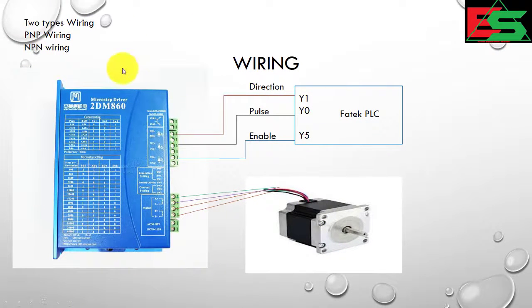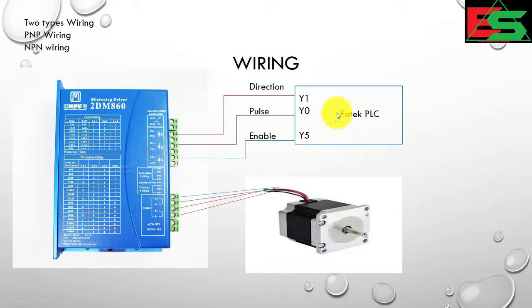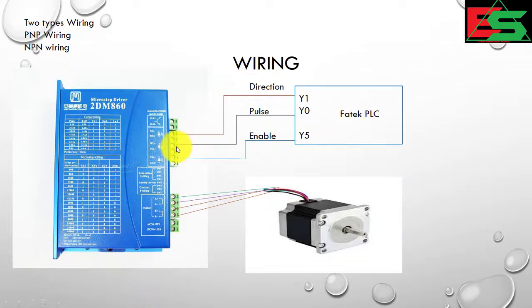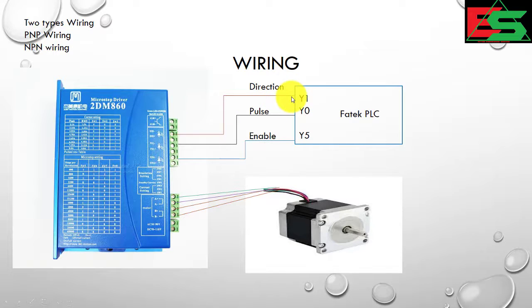Now for wiring - there are two types: PNP and NPN. In this slide I will show the basic wiring between Fatek PLC, driver, and motor. You can see here the Fatek PLC outputs Y0 and Y1. Y0 will generate pulses and I will connect it with the pulse connection strip. There are two points: pulse-plus and pulse-minus, according to your NPN or PNP wiring. To control direction of the stepper motor, Fatek PLC will give a signal on Y1.